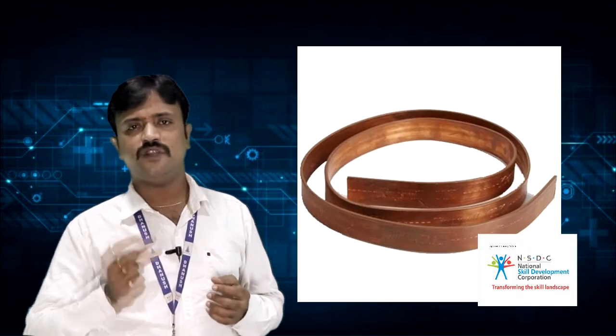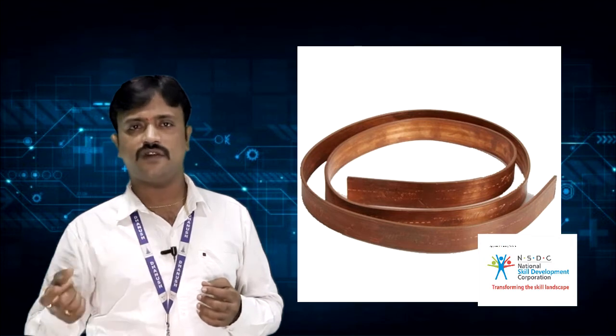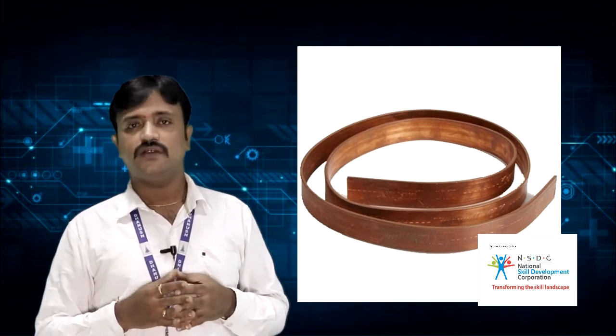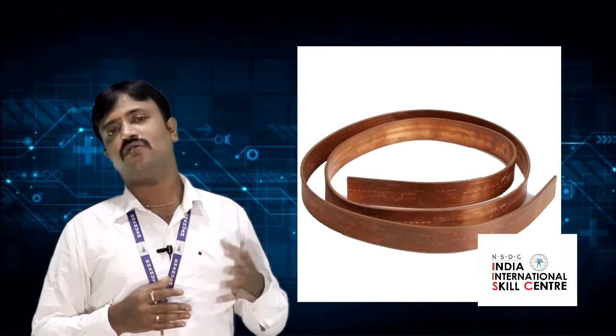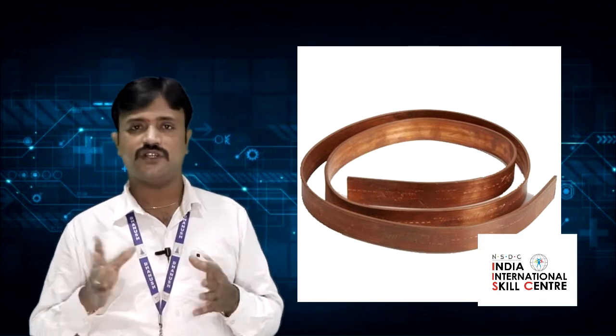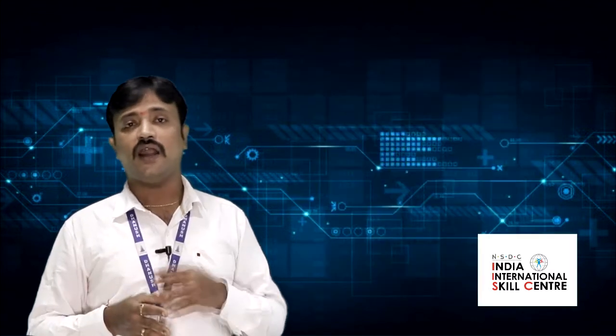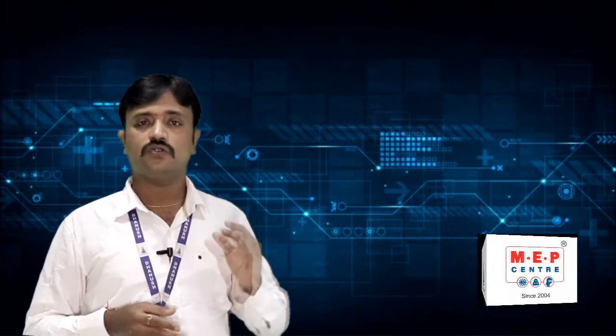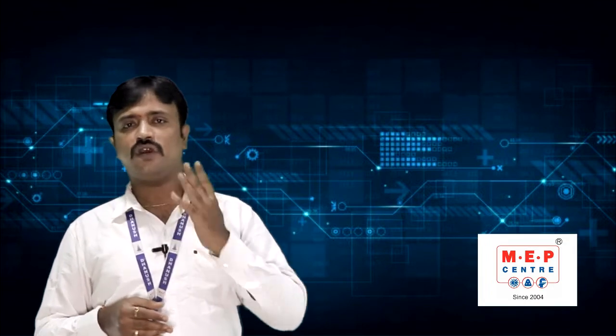Because we use aluminum strip or copper strip to ground it from the building to the earth pit. To define that strip size, we are going to do the earthing calculations, as well as the number of pits, and whether they are to be connected in series or parallel. The motto of this earthing is to maintain the overall resistance at 1 ohm to 3 ohm for the total overall building, so that leakage current will always try to flow through a low resistance path. That is about the earthing.